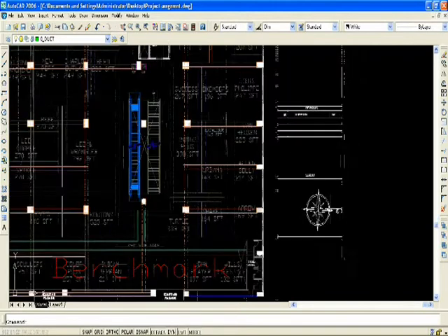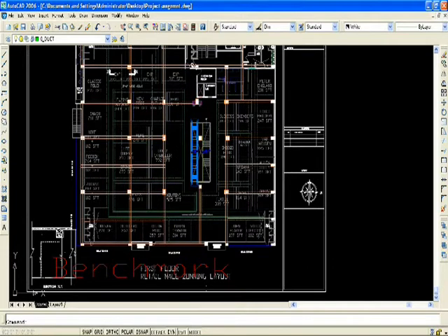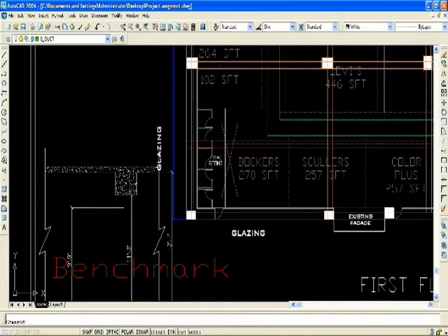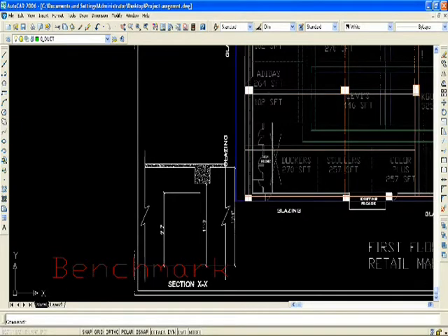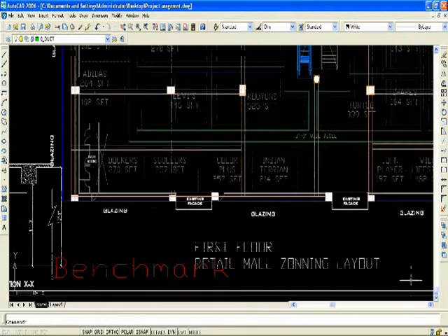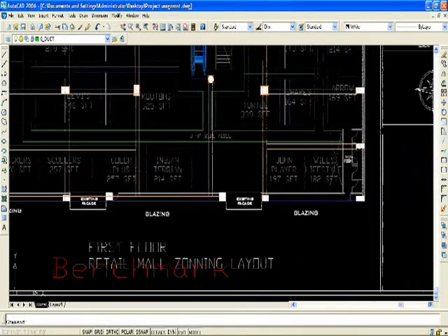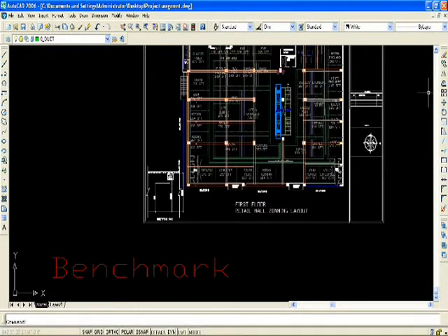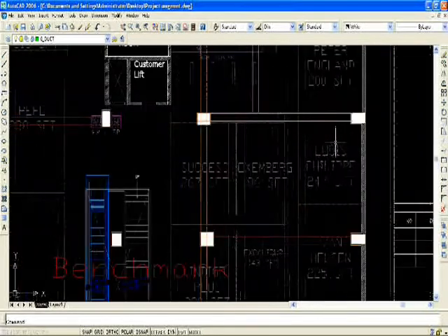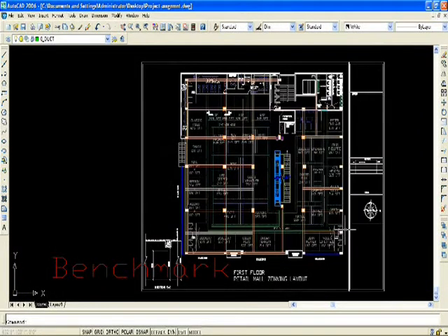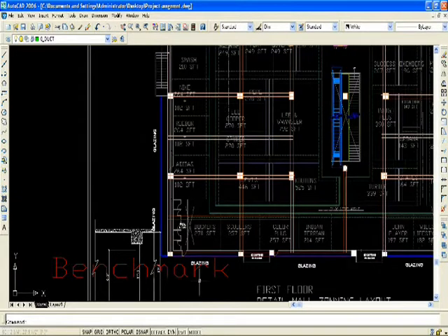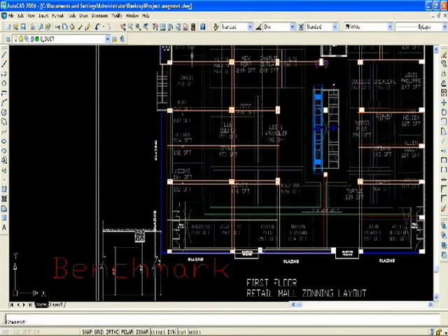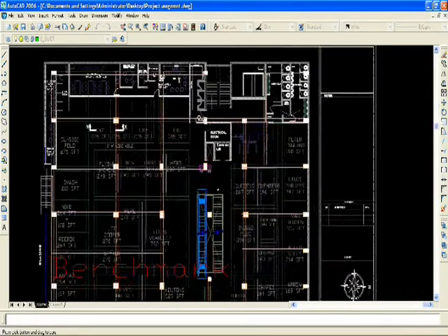We are going to use the architectural layout of the first floor plan of a retail market, which is located in Mumbai and has floors above and below, with air conditioning from a centrally located air-cooled chilling plant. We are going to consider the north side as shown in the drawing, and 13 feet height, with a 1 feet 6 inch beam, around 9 feet below the false ceiling. East and south are facing glazing glass, so we can view the inside happenings. We have been using this data for our calculation.